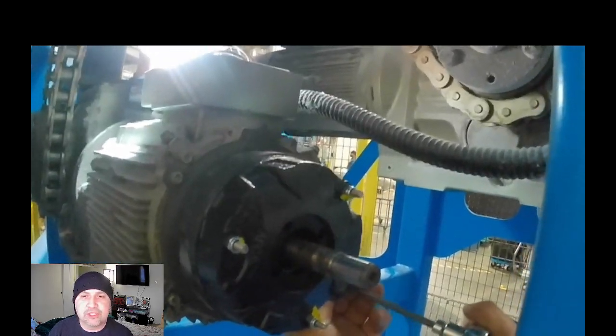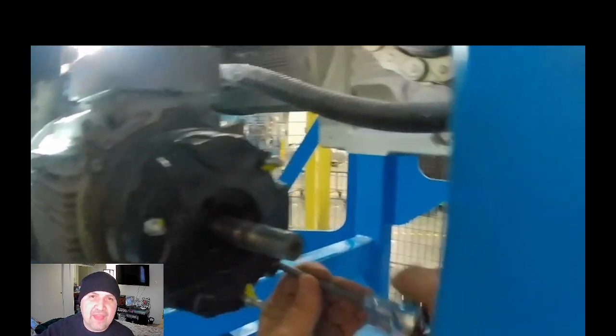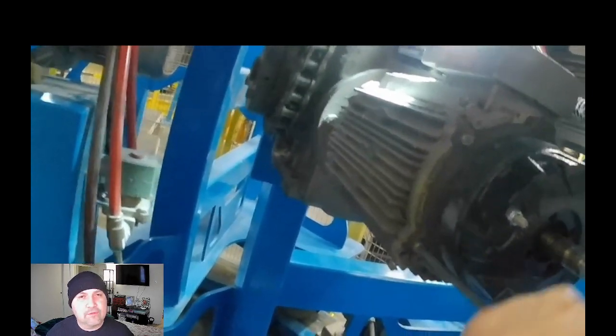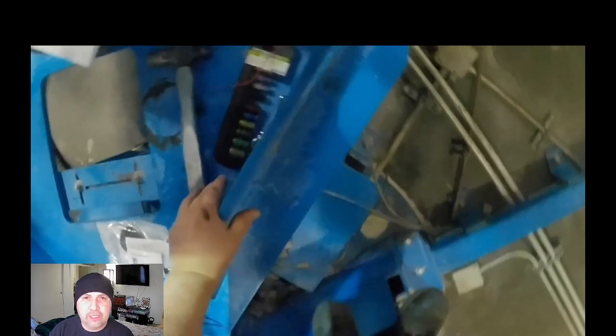That's when I made the determination to pull the brake off, and that's when I saw that the brake was smoked. But from the outside looking in, the brake looked fine. It didn't have any damage or any wear marks or anything. It looked brand new, but internally it was smoked.